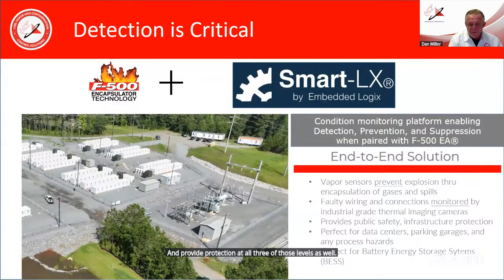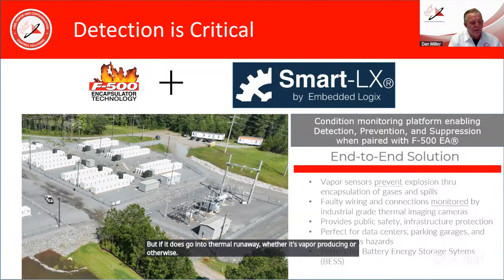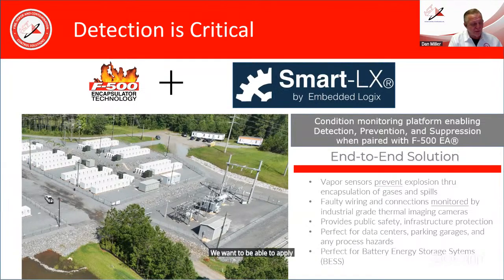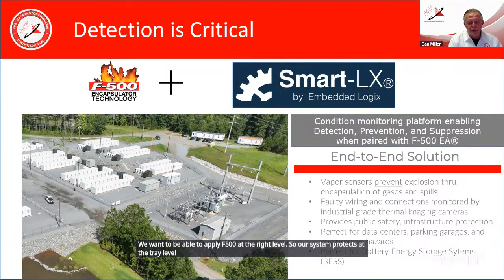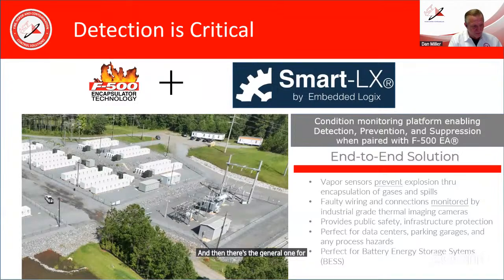And provide protection at all 3 of those levels as well. Detecting that there's a problem very, very early and allowing us to shut it down is very important. But if it does go into thermal runaway, whether it's vapor-producing or otherwise, we want to be able to apply F500 at the right level. So our system protects at the tray level in those battery racks, and then also has a head over the rack itself. And then there's the general one for the entire container as well.